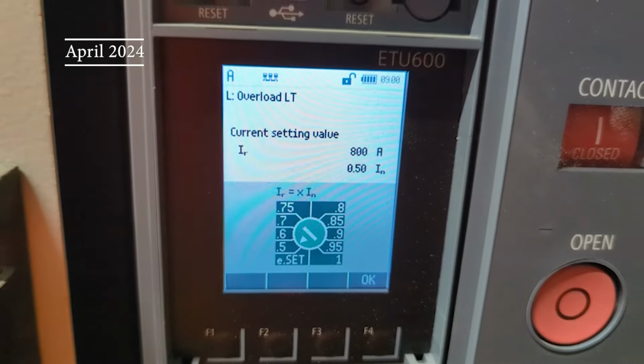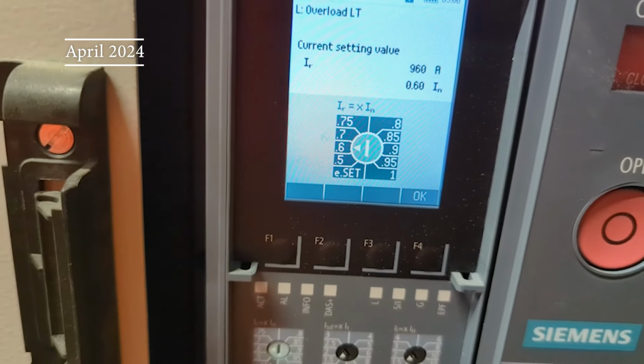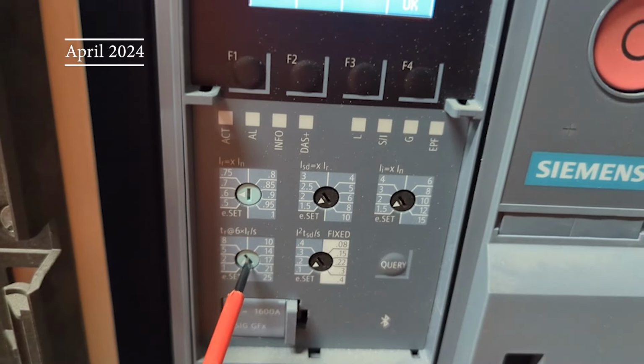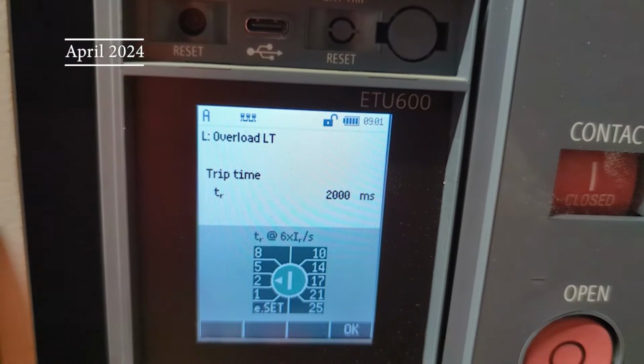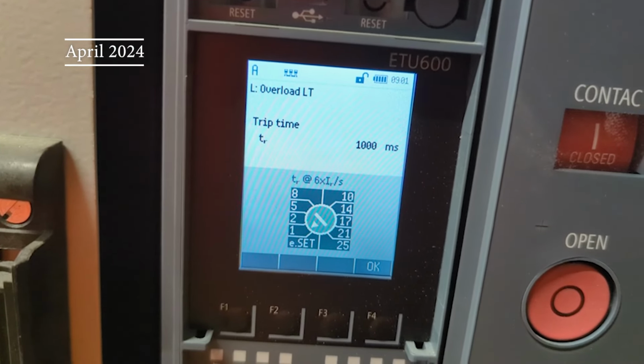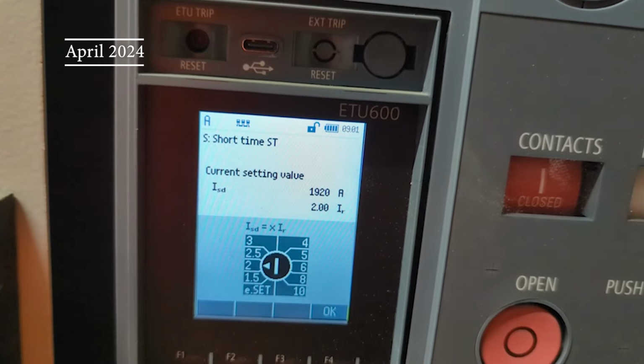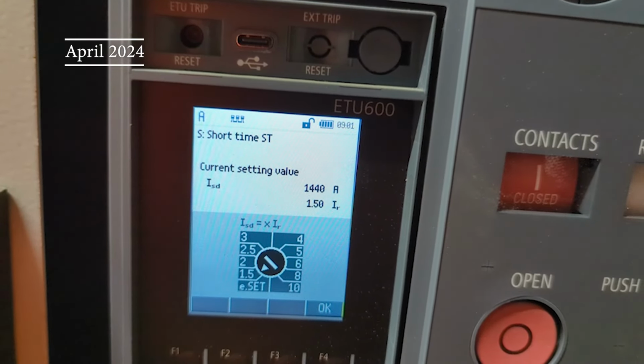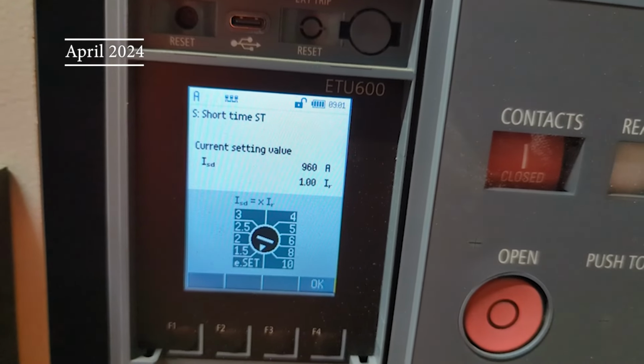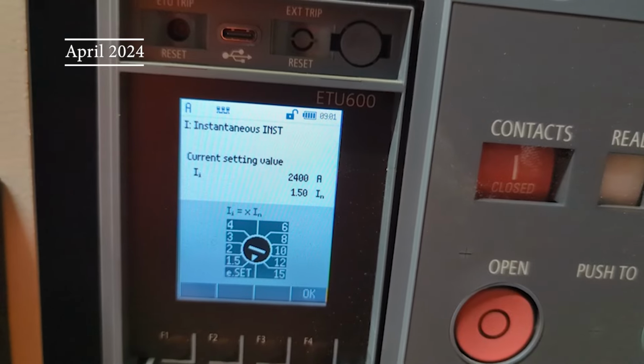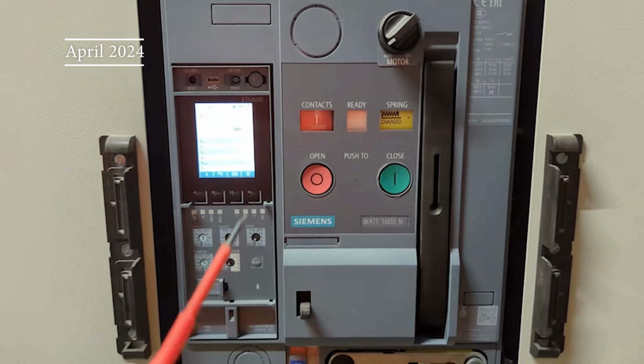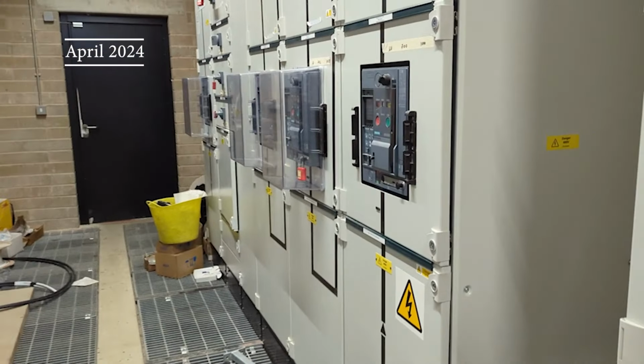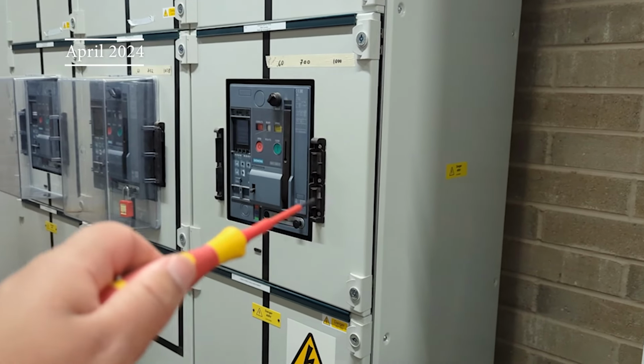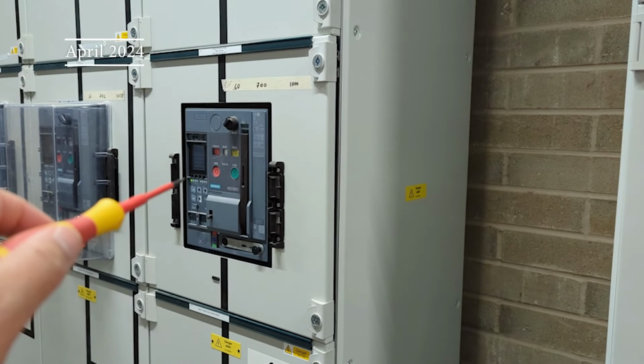So I've set this now. The overload setting on this is set at 960 amps for 1 second, and then the short time duration is set at, let's go lower, 960 amps as well, and instantaneous is set at 2400. So this one should blow as well now. Not as well, but one or the other. So I'm hoping that I can crank that one on the HPU unit back up and let this one blow.